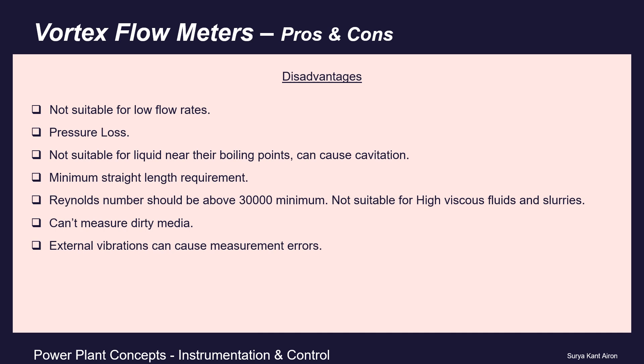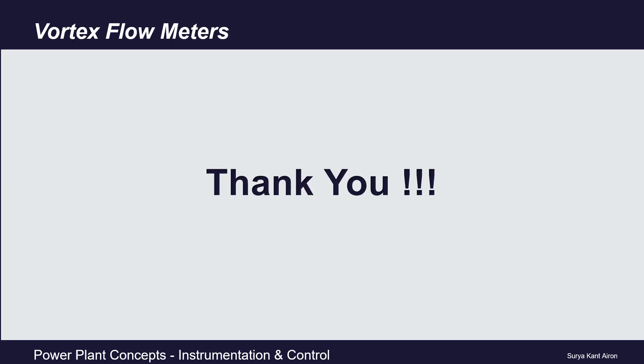Additionally, the pipe Reynolds number must be above 30,000 minimum, meaning vortex flow meters can only be used for low-viscosity fluids. They are not recommended for high-viscosity fluids or slurries, cannot measure dirty media, and since piezoelectric sensors are used, external vibrations can cause measurement errors.